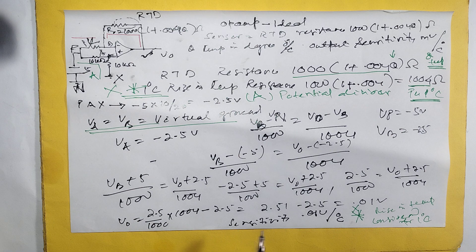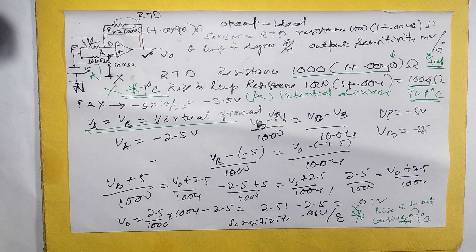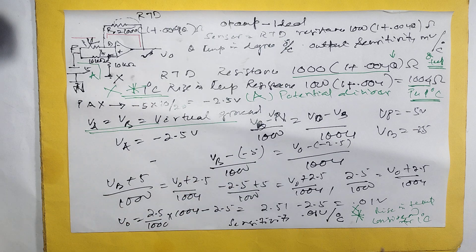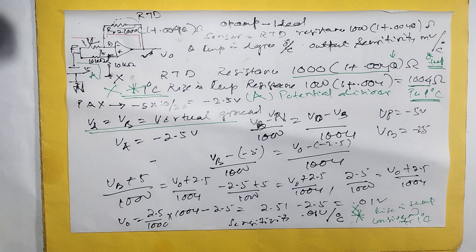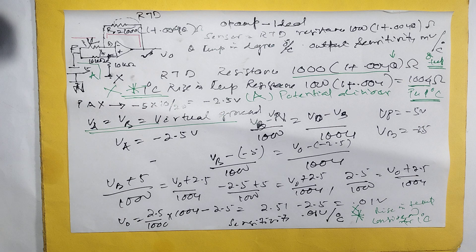Your VO will come 0.01 volt. But 0.1 volt at what location? For 1 degree centigrade rise in temperature. Because we calculate resistor for 1 degree centigrade rise in temperature. So 0.01 volt per degree centigrade rise in temperature. That is the sensitivity of RTD completed.